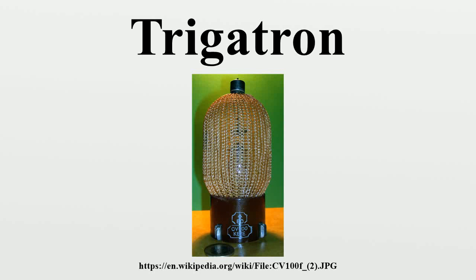A trigatron is a type of triggerable spark gap switch designed for high current and high voltage. It has very simple construction and in many cases is the lowest cost high energy switching option. It may operate in open air, it may be sealed, or it may be filled with a dielectric gas other than air or a liquid dielectric. The dielectric gas may be pressurized, or a liquid dielectric may be substituted to further extend the operating voltage.